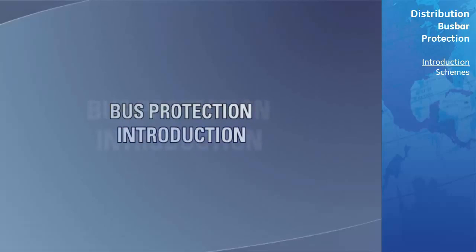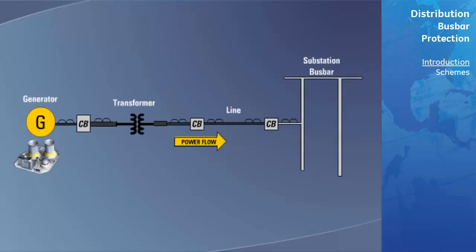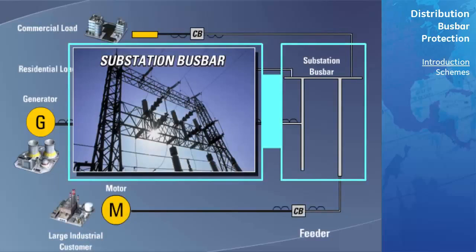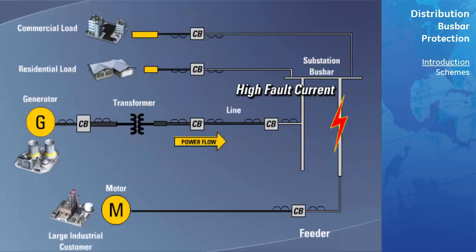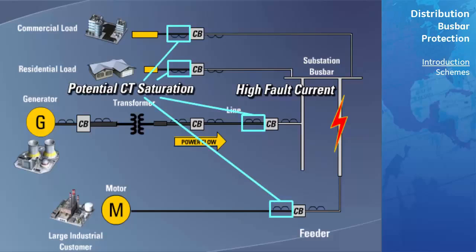One of the most common applications of differential protection is the protection of a bus. Protection of power system bus bars is one of the most critical relaying applications. When a fault occurs within the bus bar areas of a power system, fault current levels may be very high. In spite of this, some of the circuits connected to the bus may have their current transformers insufficiently rated, creating a danger of significant CT saturation and jeopardizing security of the bus bar protection system.